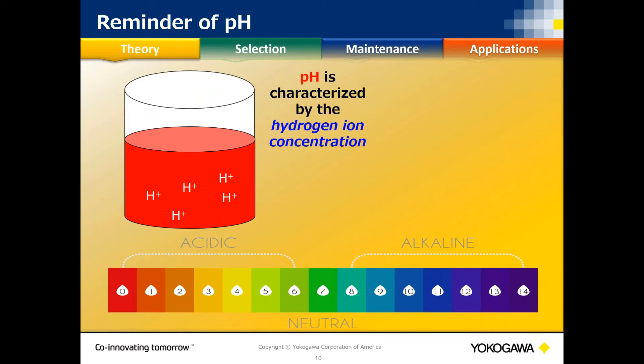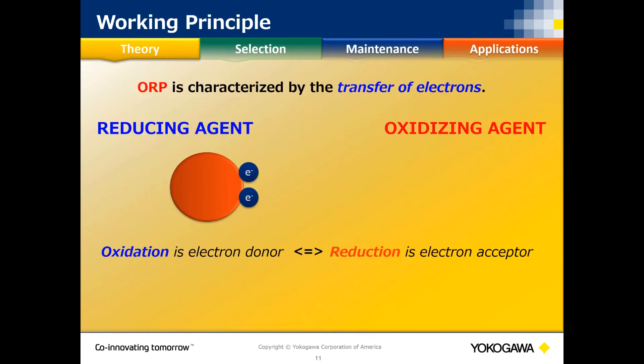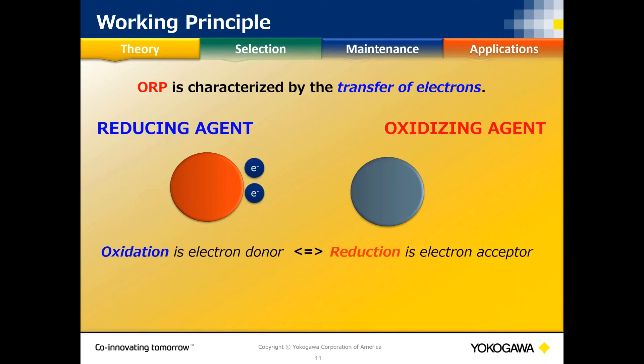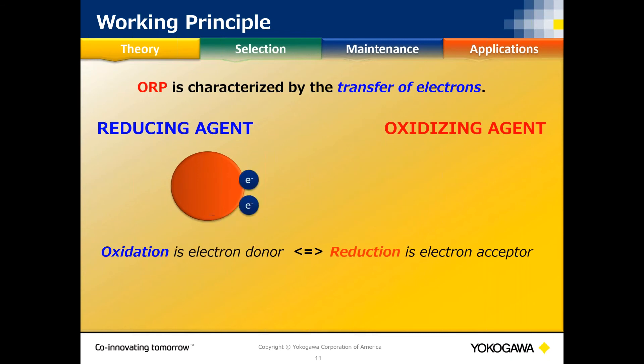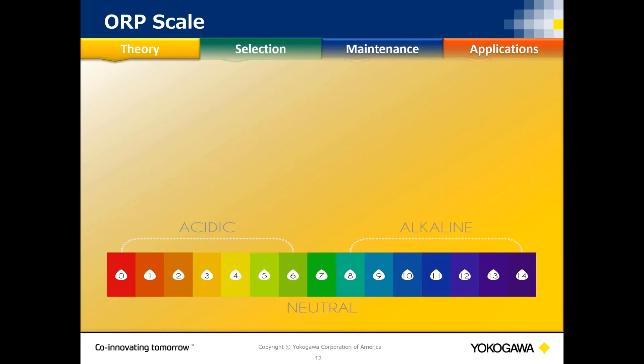ORP has a scale similar to pH. It normally goes from positive 1500 mV, corresponding to 0 pH, to negative 1500 mV at 14 pH, with 0 mV in the middle being neutral at 7 pH. Above 0 is oxidizing; below 0 is reducing. ORP is non-selective — like conductivity — we're just looking at everything in the solution causing oxidation reduction and generating a millivolt value.